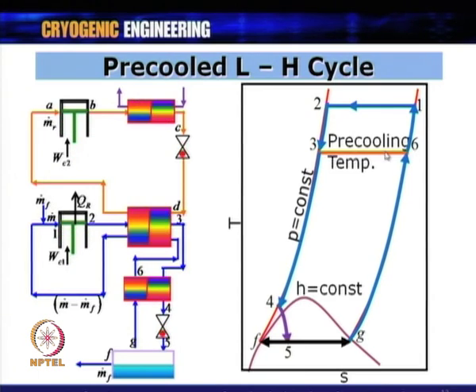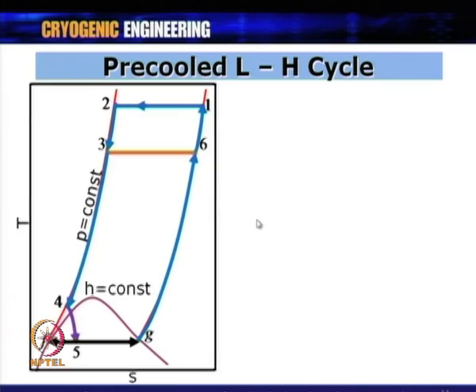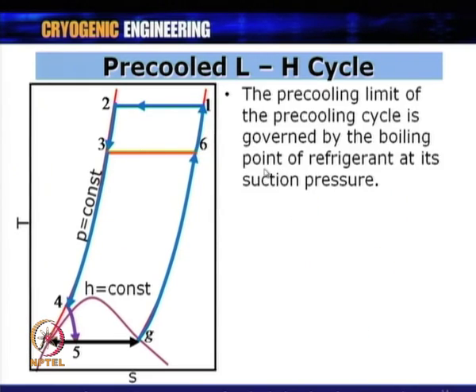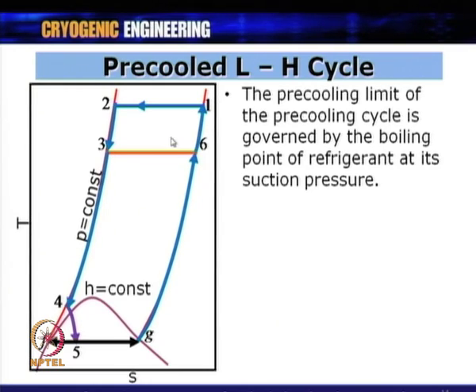The pre-cooling temperature (T3 or T6) is determined by the pre-cooling circuit — the type of refrigerant and its pressure. The pre-cooling limit is governed by the boiling point of the refrigerant at its suction pressure. For common refrigerants at 1 bar: CO2 is 216 K, NH3 is 240 K, and R134A is 247 K.